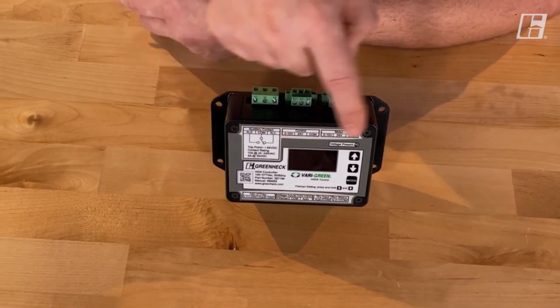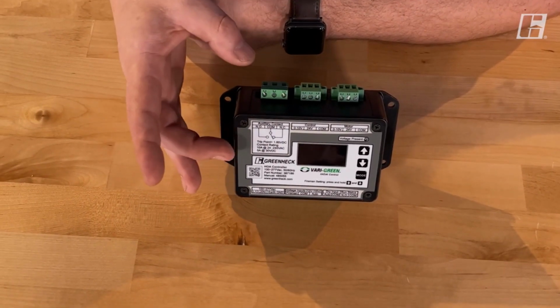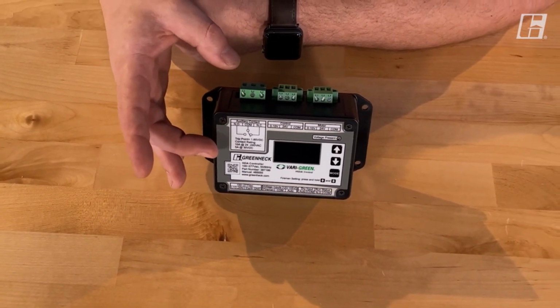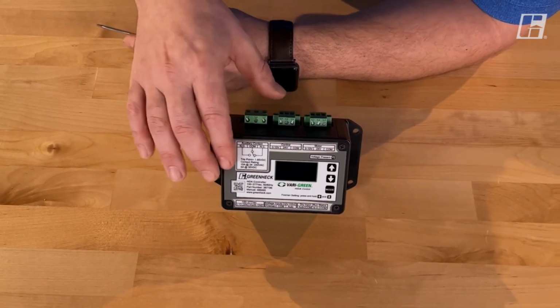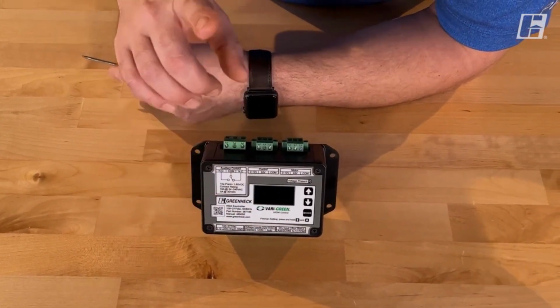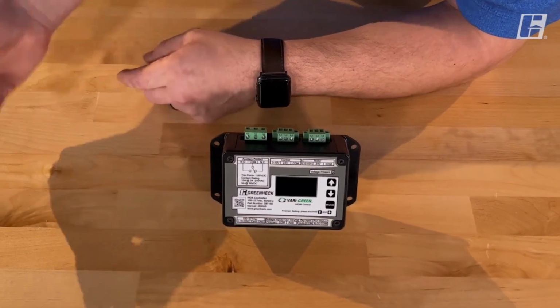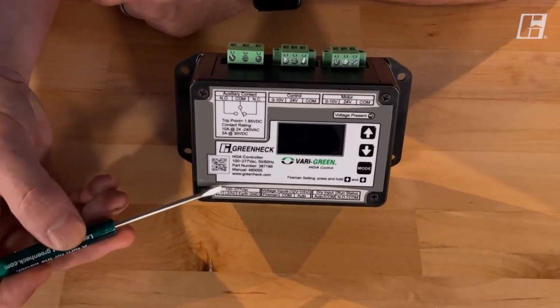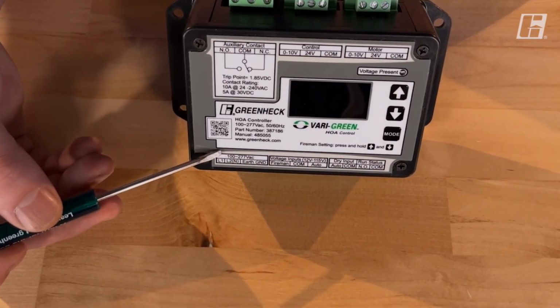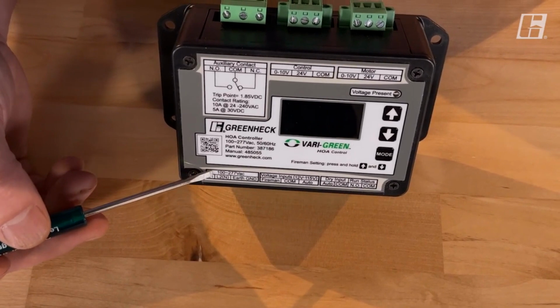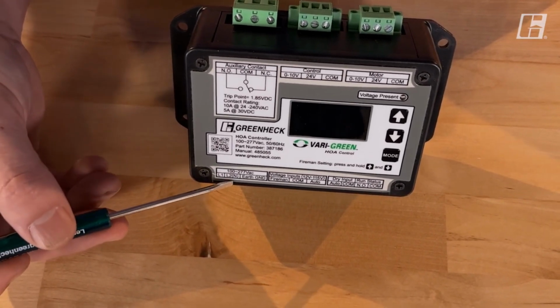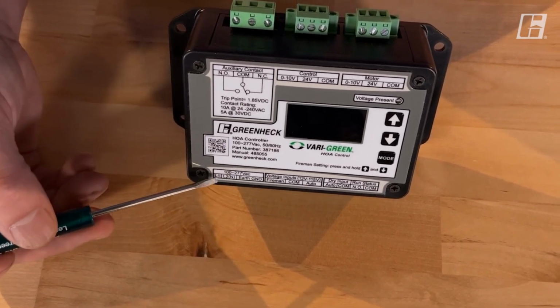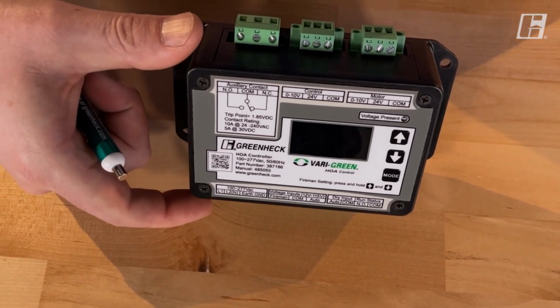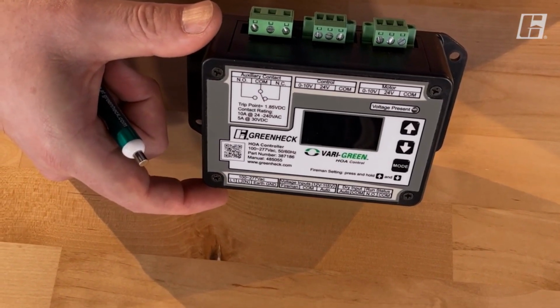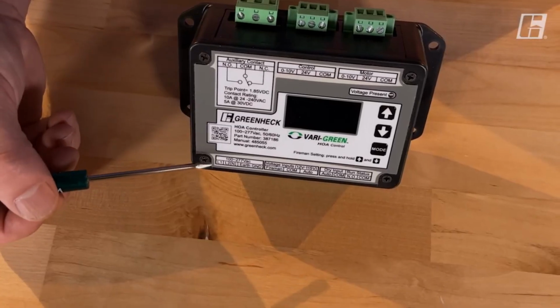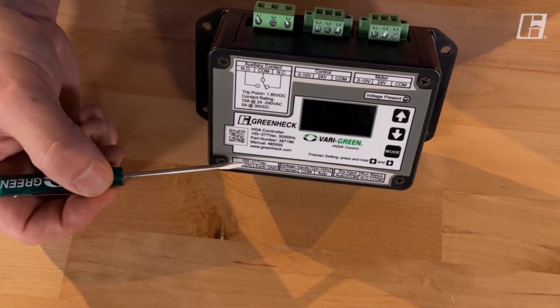Now these top 3 terminals are the exact same on the Vari-Green HOA as they are on the Vari-Green transformer. So really, they're exactly the same on the top. Where the difference is, is across the bottom. Let's go there next. Here we have to power this HOA unit, and it'll accept anything from 100 to 277 volts. There's a line 1, a line 2 neutral, and an earth ground. So wherever this box is mounted, whether it's in a mechanical closet, in an enclosure, along with other electronics, we just need to provide power so that this thing will run.